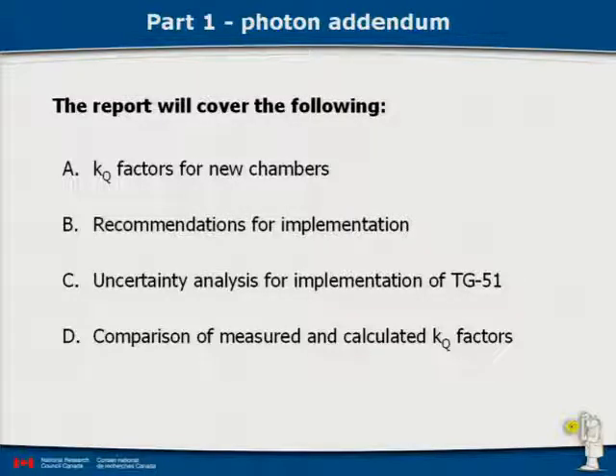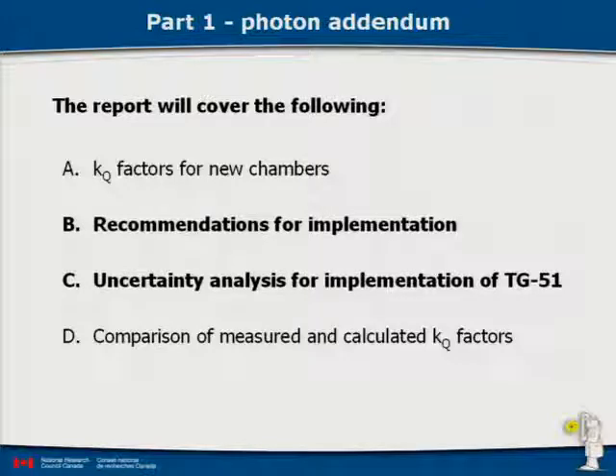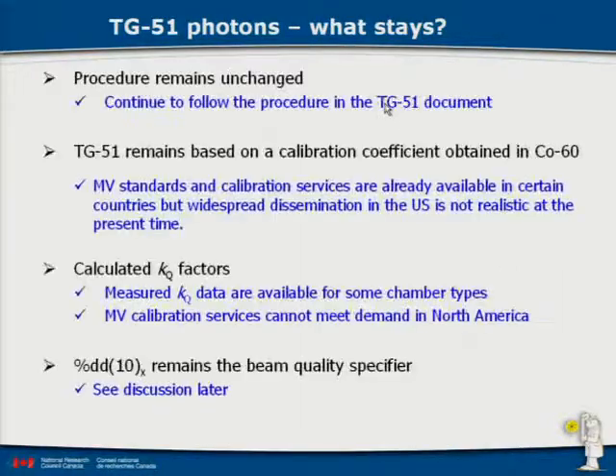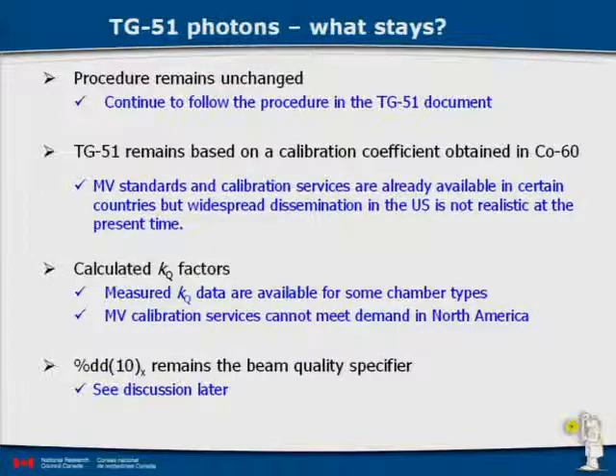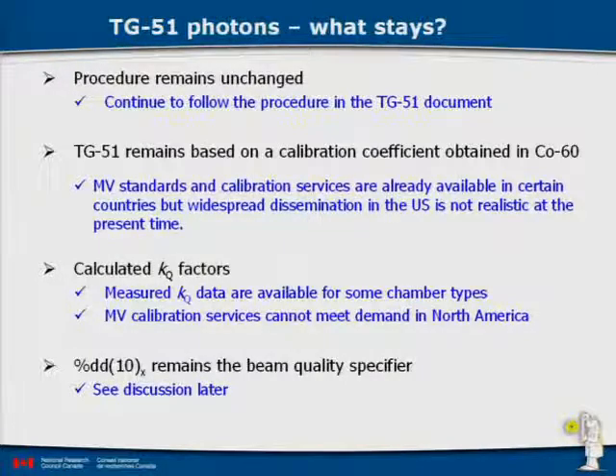For this presentation, I'm going to look at the recommendations for implementation and the uncertainty analysis, as those are the ones you'll be most interested in. Just to be clear about what stays with TG51: the procedure remains unchanged. It remains based on a calibration coefficient in cobalt-60. The ADCL operation won't change — they'll still provide a calibration coefficient in cobalt-60. Some laboratories, including the NRC in Canada, can provide MV calibrations, but the effort required for 1,500 clinics isn't really there. We'll continue using calculated KQ factors, and DD10 will remain the beam quality specifier.